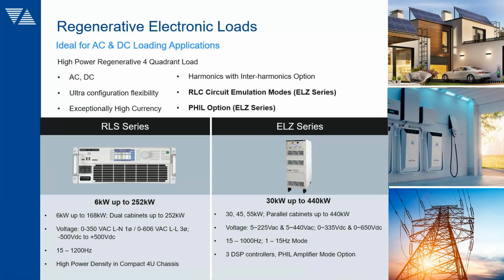Similar power levels, with additional features specific to loads, such as circuit emulation on the ELZ series and the PHIL option on the ELZ series. For load applications, being regenerative is very energy efficient and cost efficient, especially at higher load levels where you're not dissipating that energy anymore—you're putting about 90% of it back onto the utility. So you can quickly recoup your equipment investment cost if you have large loads you're burning in or testing for long periods of time, seeing significant energy savings.